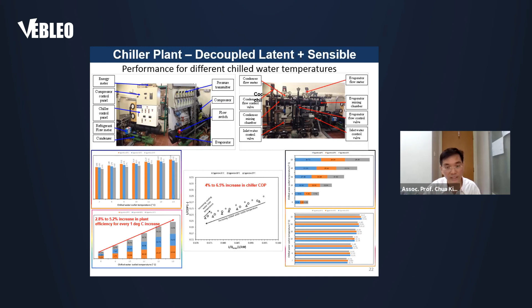So previously, if you were providing 5 to 6 degree chill water to your air handling unit room, now you are providing it at about, let's say, 15 to 16. We ballpark it to 15 to 16. That is a temperature difference of about 10 degrees. You multiply that by 3%. Let's be conservative. Easily, you can realize about 30% energy savings using just this kind of new technology that we can put into the AHU room to remove the moisture from the air. So that is how impactful it can be.